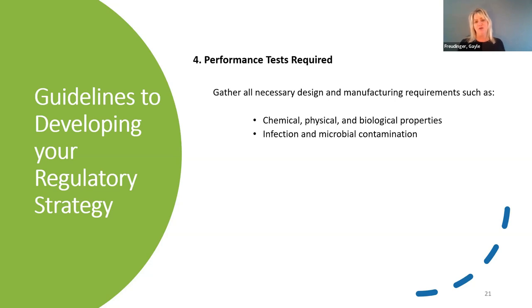And I don't know, Shana, do you want to kind of elaborate on that a little bit? Truly. The things you have to be careful of, like there's a whole system of toxicological testing, and in medical devices, it's actually called biocompatibility, because you're seeing how compatible this device is in situ in the body. And one of the basic tests, for instance, is cytotoxicity. Does the device cause cell death just by being in contact?